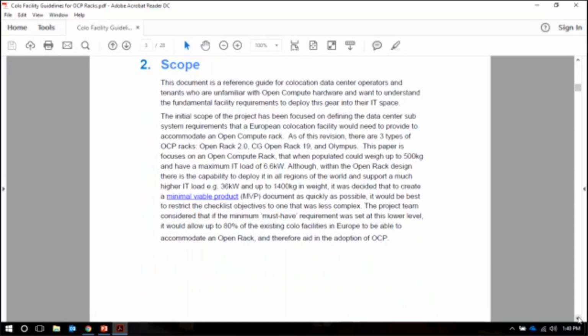The other thing we're looking at with this document is the worst case of open compute gear you can deploy—it can be very dense and very heavy. If we said you have to be able to take 36 kW and 1,400 kilograms per rack to deploy open compute gear, there'd only be a handful of colocations in Europe that could actually do that. So they looked at what might be a lower end, while still explaining the full range.